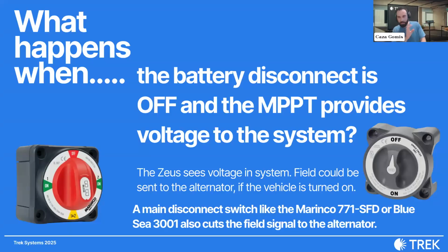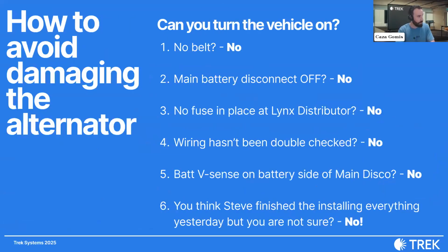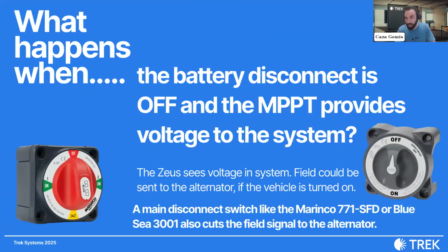This is primarily for systems that have internal BMSs. If you have a Lynx BMS, you don't need this. But if you don't have a Lynx BMS, even if you're using another external BMS like the VE Bus BMS or something similar, it's really imperative to use one of these switches. What are we solving for? We're solving for the specific circumstance where the main disconnect switch is off and solar is for some reason still coming in and providing voltage to the system. We want to ensure the regulator doesn't send power when it's not supposed to, and the only way to really do that is to use these switches in the system.